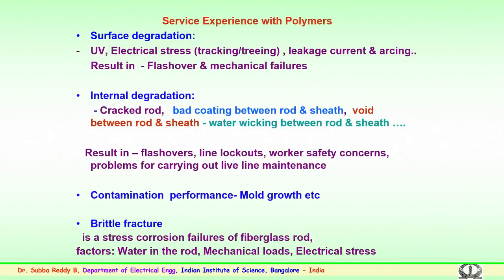With service experience over three decades since the initial composite insulators were used for transmission systems, they are now widely used in several countries, even for the EHV and UHV range. There is experience with polymers over a period of time. Initially, failures were noticed because of several issues, like surface degradation of the polymer surface. This could be because of ultraviolet radiation from the sun over a period of time.